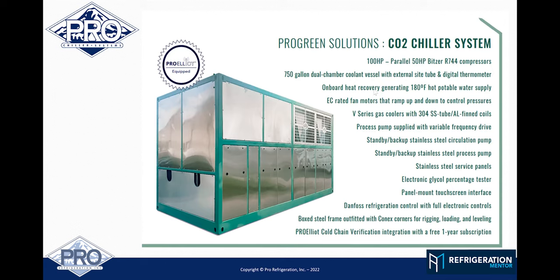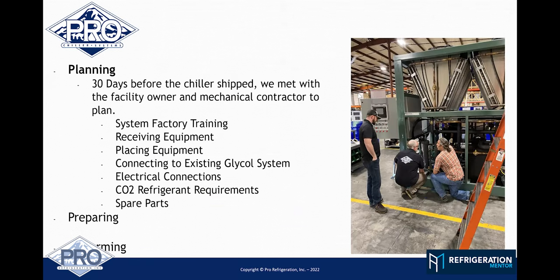So with the glycol, do you use a brine, do you use glycol, what do you use for your coolant medium? We use propylene glycol, or a propylene glycol and water mixture, depending on the customer's operating temperature, which determines what our evaporator temperature is going to run at.